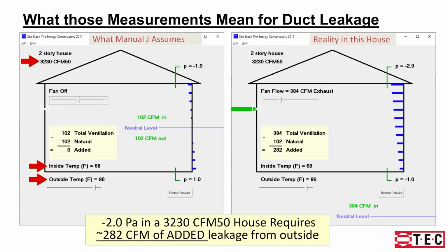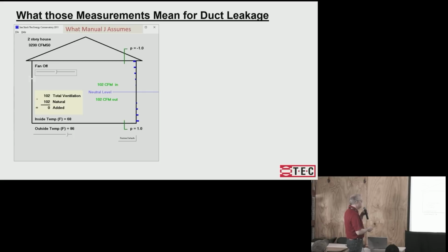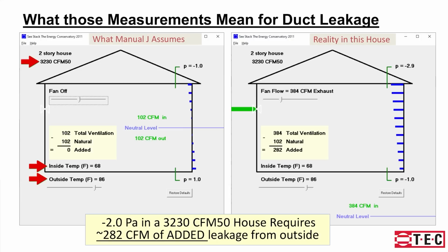And in this case, we've set it so it's 20 degrees warmer outside. So this is actually the same as if it's 75 inside and 95 outside. That's a 20 degree difference. That's what we're simulating here. And this simulation tool will tell us what we expect to see: we expect to see 102 CFM of air leaking in the top floor, approximately, and the same 102 CFM leaking out the bottom floor.